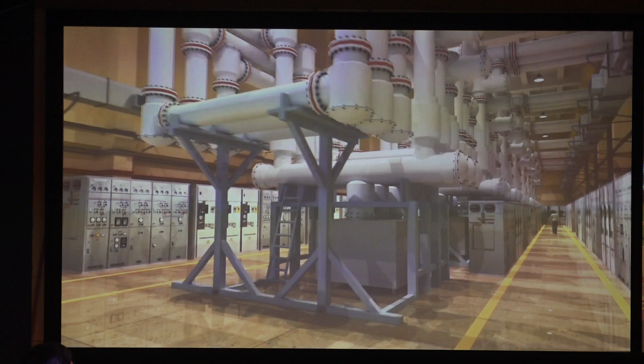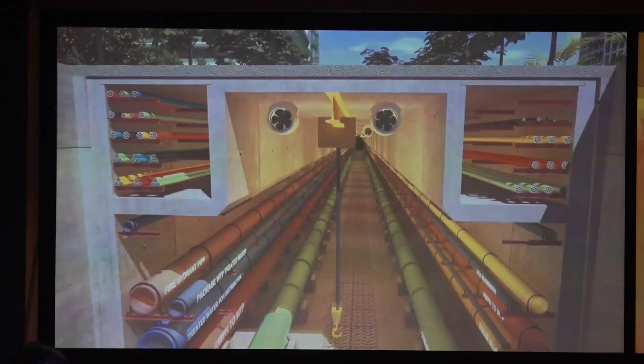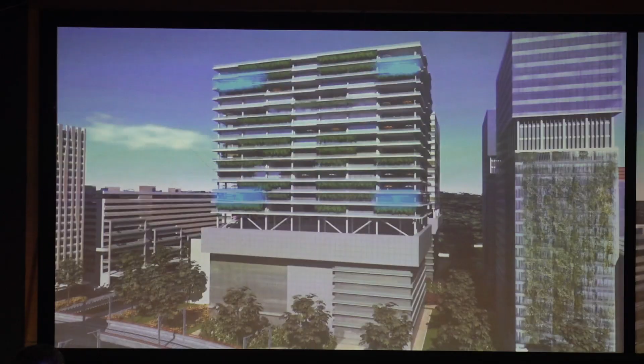20% of total load is assumed as emergency requirement and shall be generated through an in-house gas-based power plant. Power distribution will be via utility trenches through HT cables at 33 kV. Compact substations, depending on load density, shall be placed at refuge floors of tall buildings to enable connectivity to all floors and minimize distribution losses.